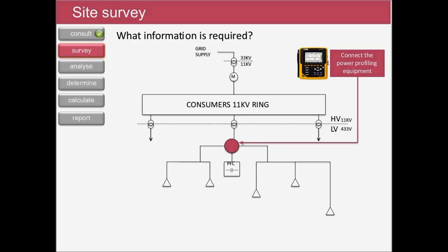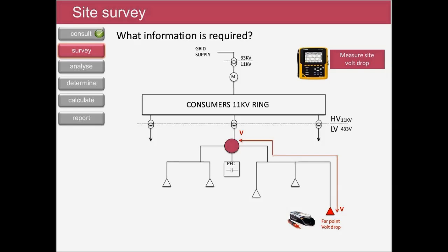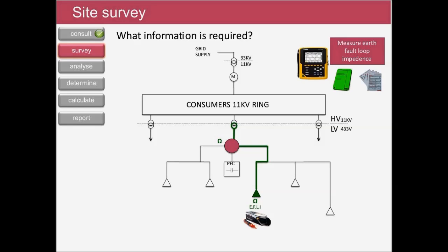The logging should be carried out for a minimum of 7 days, but much more importantly than that, it should be carried out during a typical consumption period in order that useful profiling data can be collated. During this period, the site volt drop should be measured so that an evaluation can be made on how a voltage reduction may impact the load-bearing equipment at far points of utilisation on the network. Earth fault loop impedance values should also be spot checked to verify that any reduction in voltage is not going to compromise the values tabulated in BS 7671. And more importantly, the 80% values enforced by some of the third-party accrediting bodies.